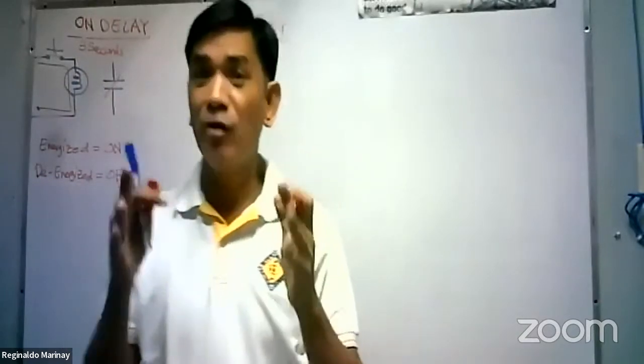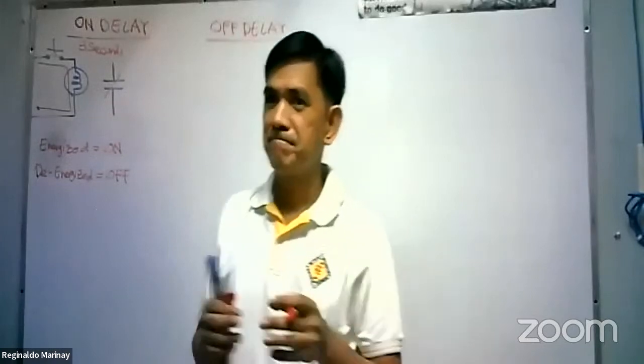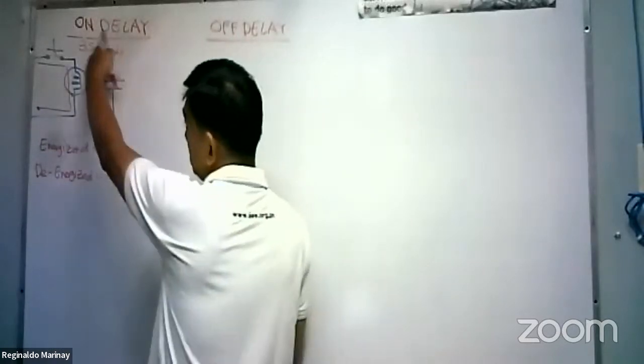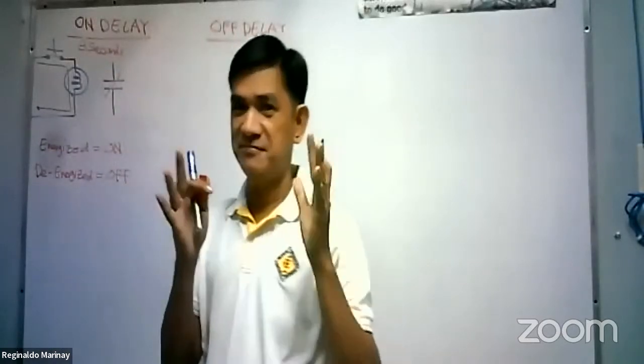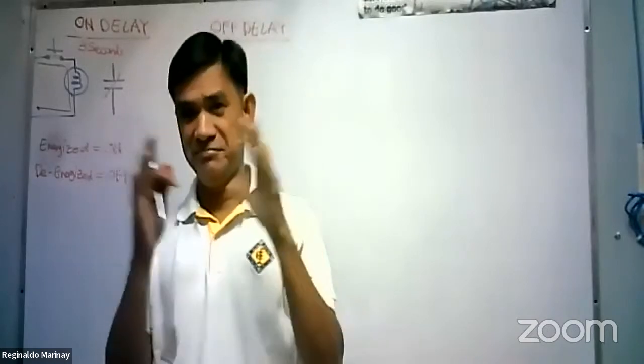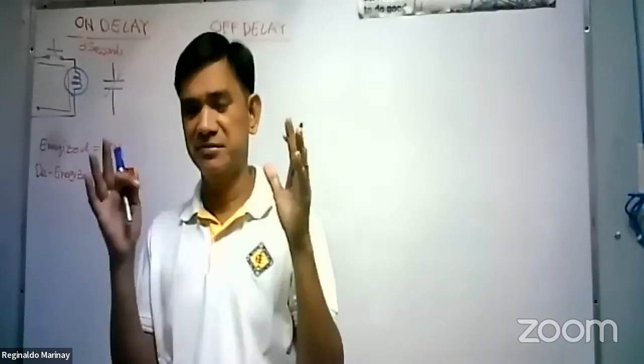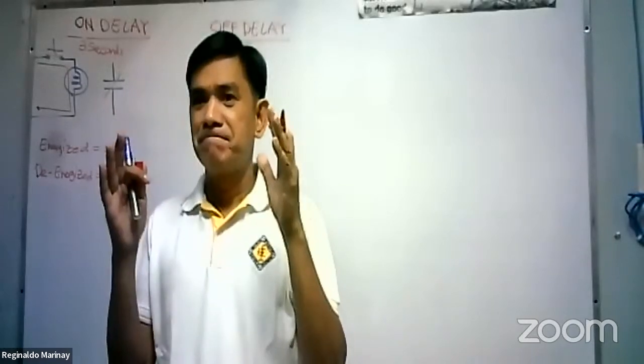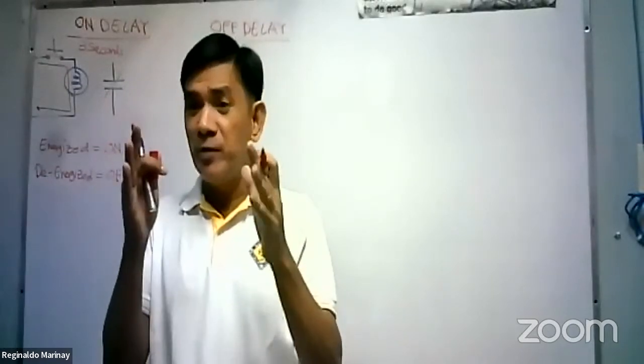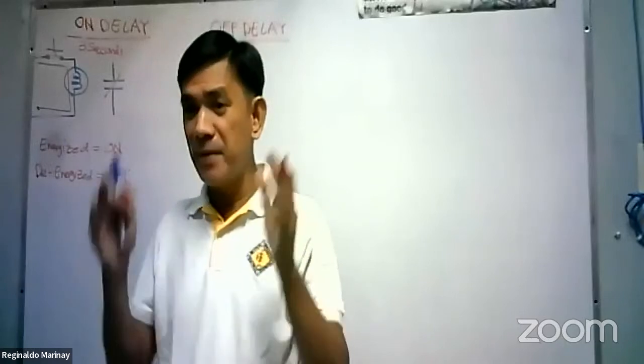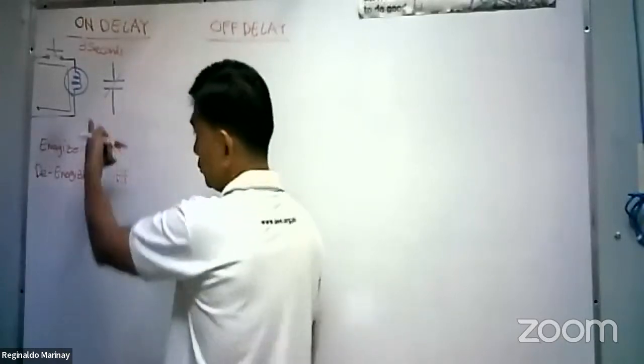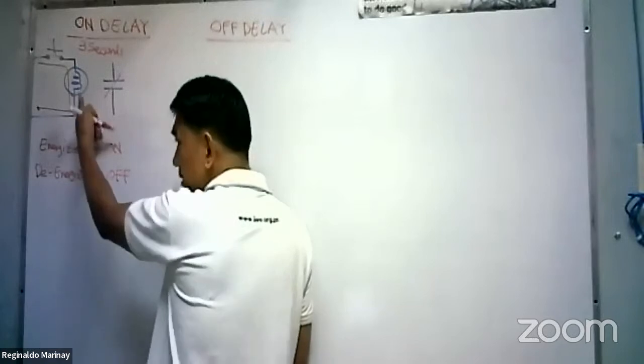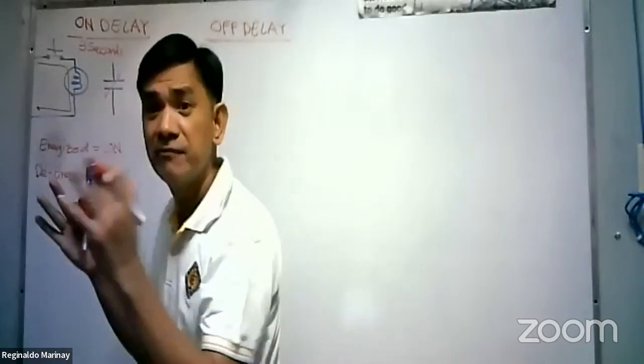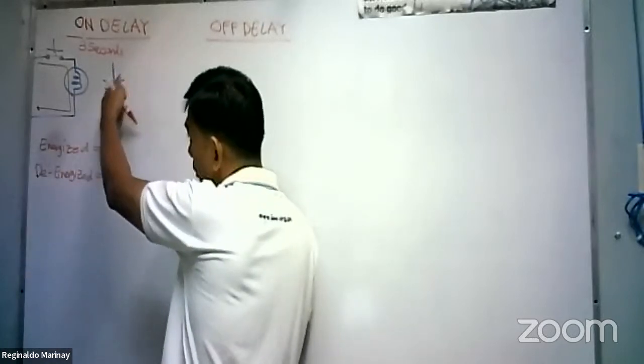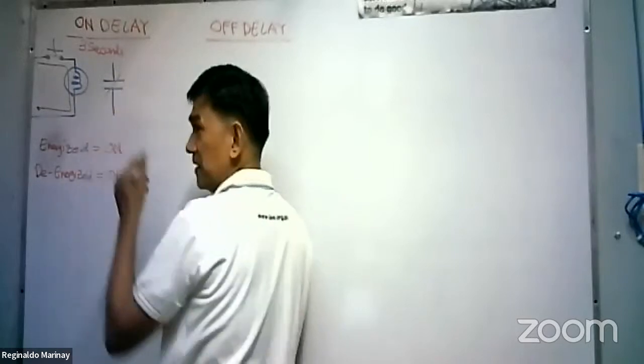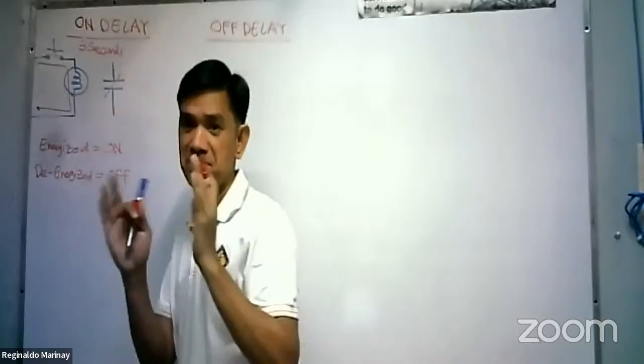That will happen for the on delay. Meaning the delay is on. There is a delay. It will not act right away. It is opposite with the magnetic contactor. The magnetic contactor, once you energize this holding coil, right away, there is no delay. That will become closed. Once this becomes energized, there is no delay.